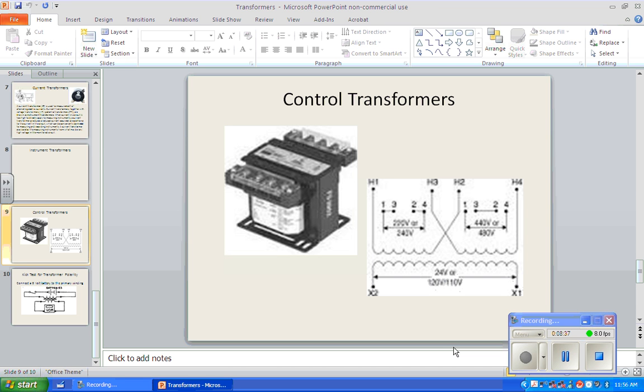If you're using an outside lighting circuit for your control circuits, it presents a danger because you might have your power off and think all your power is dead, but you might have a control circuit that's live - so that's not so good. Common control is where you have line voltage from your primaries going through your control circuit. That might be 277, 480. Probably not a good thing to have on your contacts and touch them and get 277, 480 across your fingers.